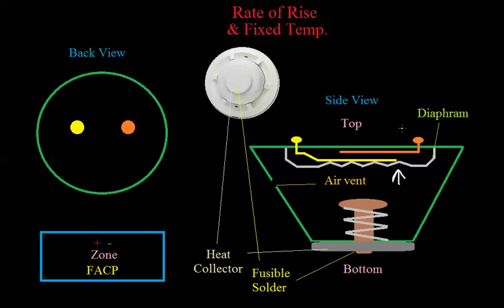Rate of rise heat detectors typically go into alarm when there's an increase in temperature of at least 15 degrees Fahrenheit per minute — that's based on the properties of the metal and how quickly it bends. If the temperature were to increase slowly, there's a little air vent in the detector, so some air will escape. If the temperature increases faster than air can escape through the vent, that's what expands the diaphragm, pushes it up on the contacts, and shorts them.